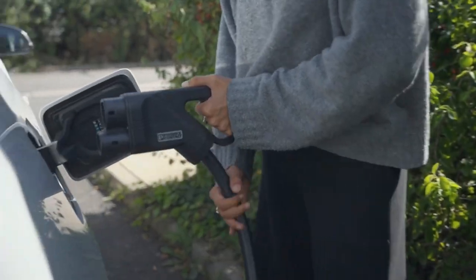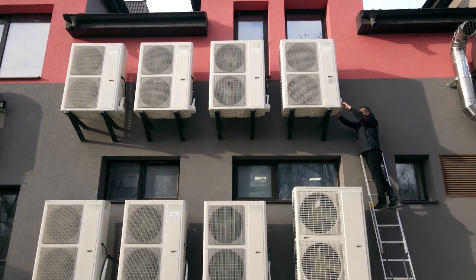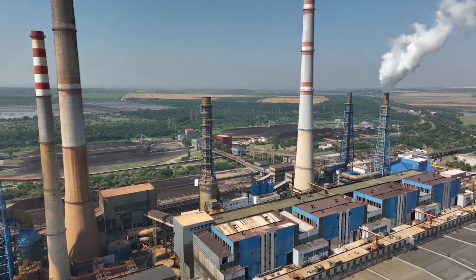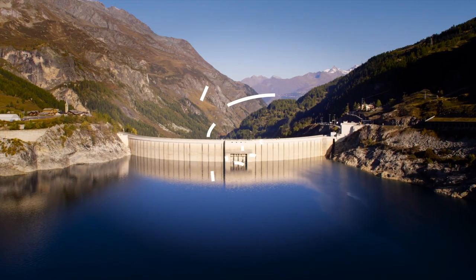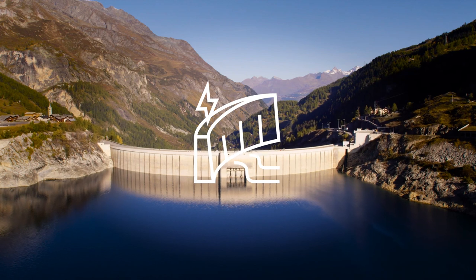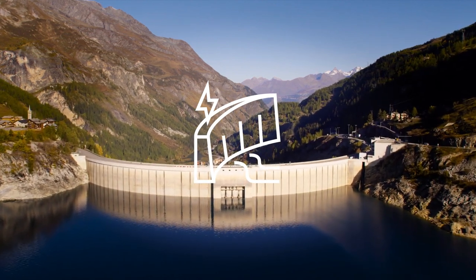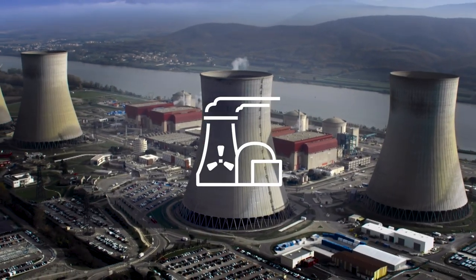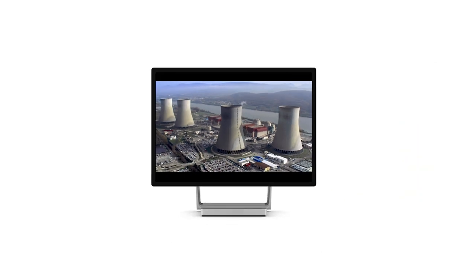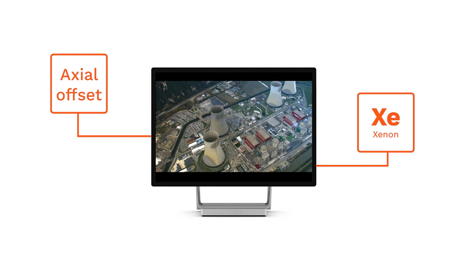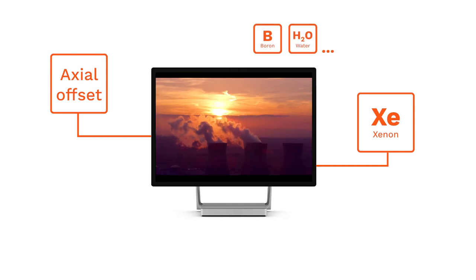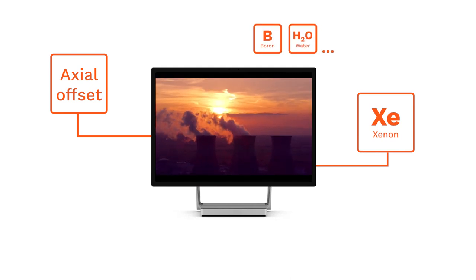For the electric grid to remain stable, production must always meet demand. As of today, utilities can only rely on the flexibility of their gas, coal, and hydroelectric power plants, whose output is easily monitored and modified. Nuclear reactors present specific challenges when used for flexibility, such as the control of axial offset, xenon, or chemical conditions within limited boundaries during power transients.